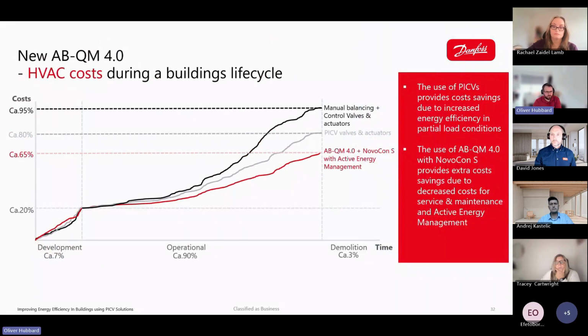So here we actually have a cost breakdown of them. Most often HVAC investments are judged on cost in the development phase, so the purchasing price and the installation costs. But more relevant is to look at the actual cost during the operational phase and the long-term building efficiency view. Here you can see that manual balancing valves cost about 20% in the development phase, whereas 75% of the cost of the building cycle is on the manual balancing valves. When you just change that to PICVs and actuators, it reduces it by 15%. And with PICVs and smart actuators with active energy management, it reduces it by an overall 30%.